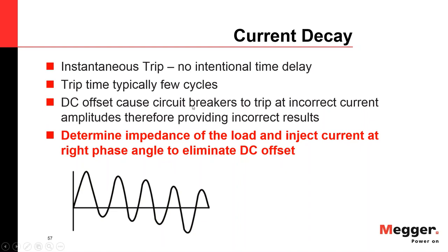No asymmetrical component. So it would be very nice to have a tester that can actually measure all of that, and have a source that can be turned on in a way that the DC offset is fully compensated.